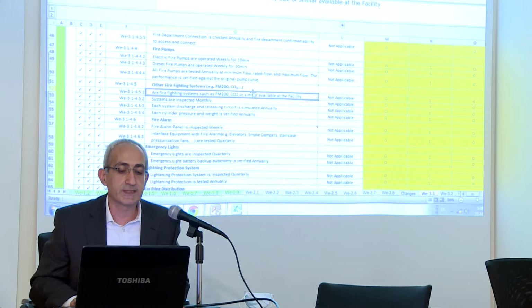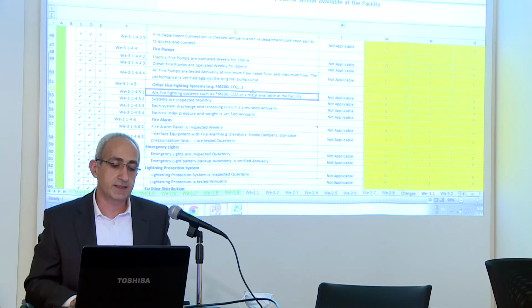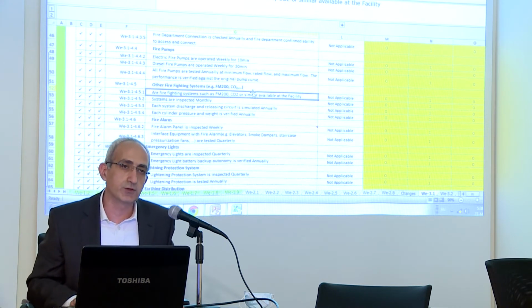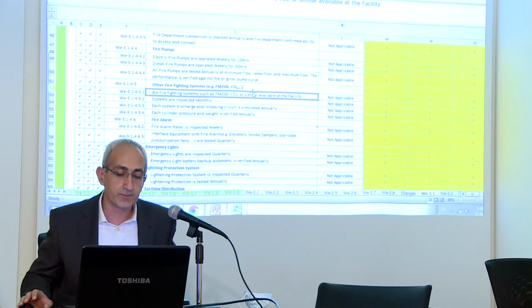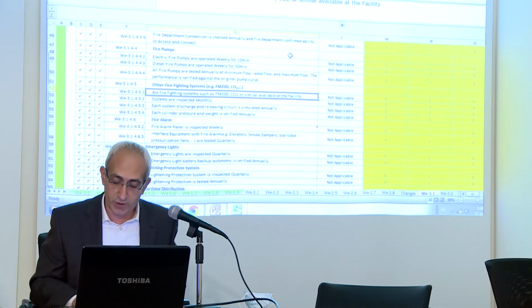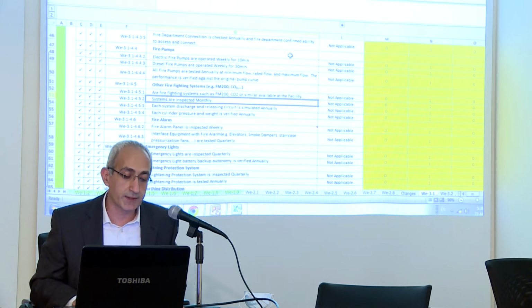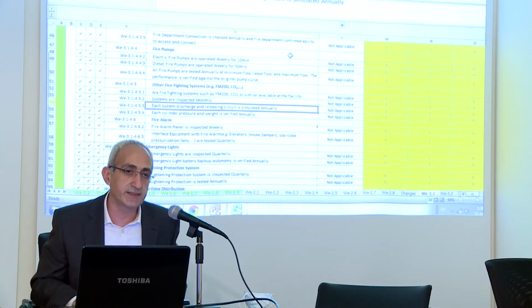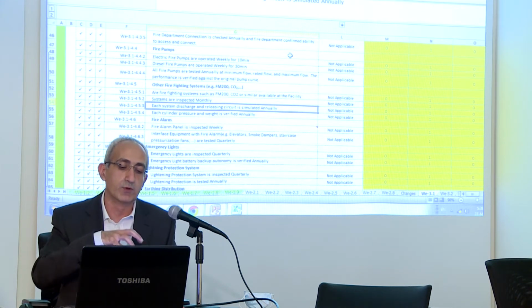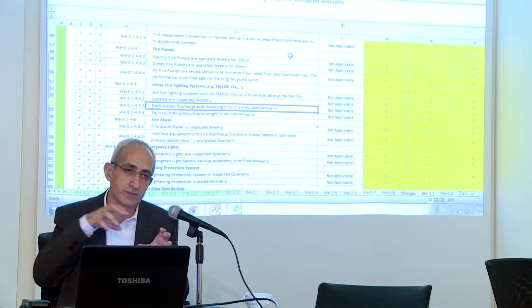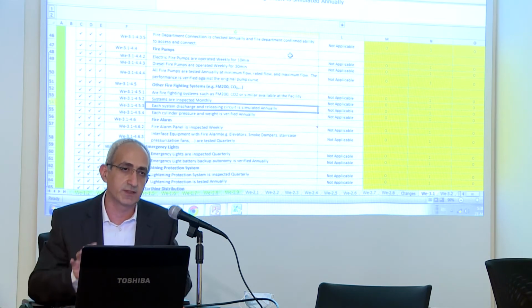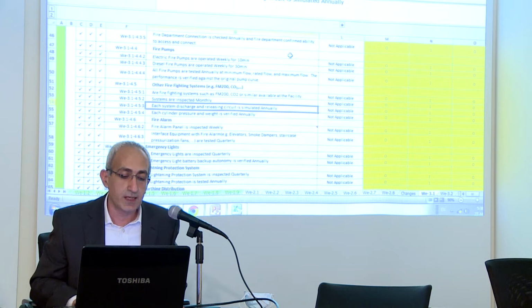Other firefighting systems that you may have in the facility are FM200, CO2, and other systems. So if these systems are available, the following are required. Systems are inspected monthly. System discharge and releasing circuitry is simulated annually. So we remove the activation head from the cylinder itself and we simulate a fire. And each cylinder's pressure and weight is verified annually.